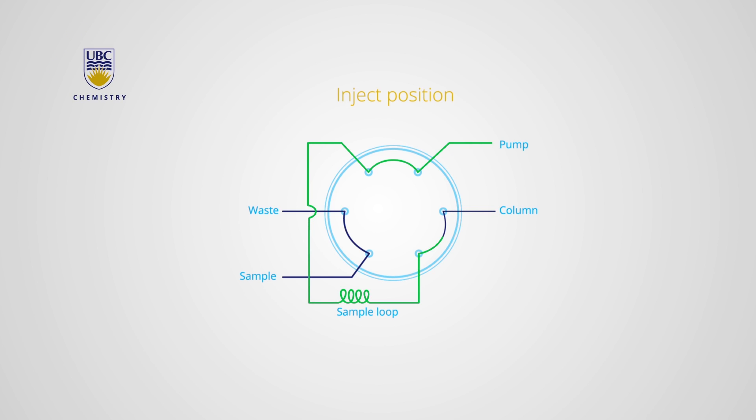When the injector position is switched from load to inject, the sample loop becomes part of the overall mobile phase flow path, and the sample passes through a capillary to get to the column.